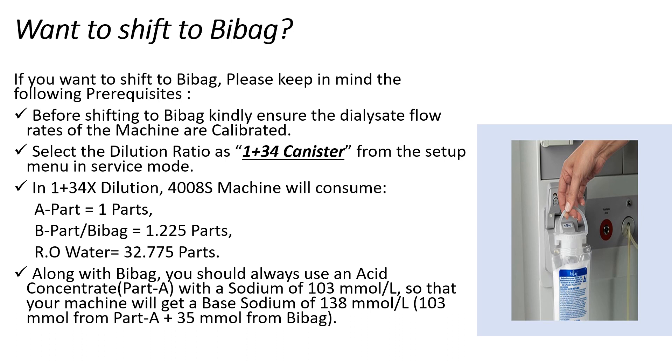Next, you should select the dilution ratio as either 1+34 canister or 1+44 X from the setup menu in the service mode. In India, we are using 1+34 canister dilution ratio as the standard mixing ratio for Bi-Bag. In this ratio, the machine will consume 1 ml of A-Part, 1.225 ml of Bi-Bag concentrate, and 32.775 ml of RO water.